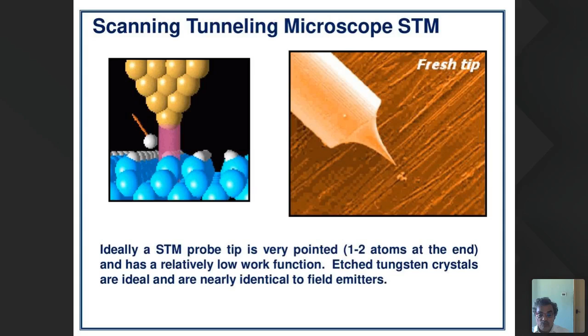There are 4 modes of operating the scanning tunneling microscope. One is constant current mode, which is the most widely used. Here, the tunneling current is kept constant, so the position of the tip must be moved up and down. That means the tip will move up and down, but the current is kept constant. This movement is recorded, and then the topography of the specimen can be inferred from the varying height. Because the current has to stay the same, the tip moves up and down, and that movement is recorded. The other counterpart is constant height mode.